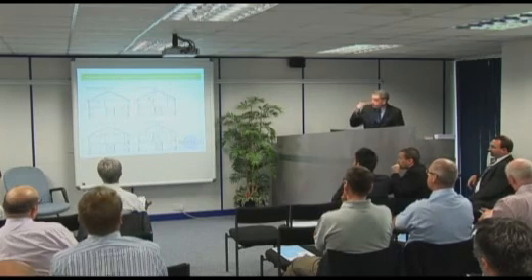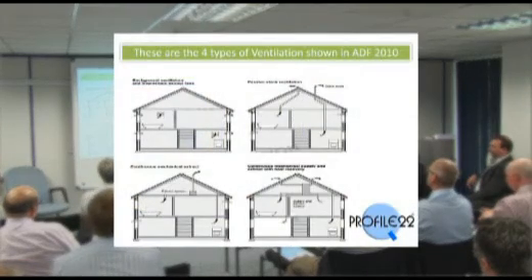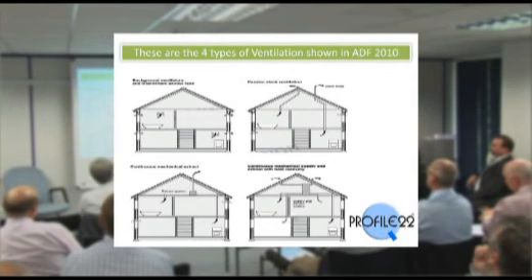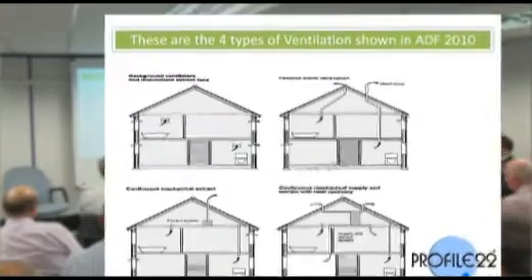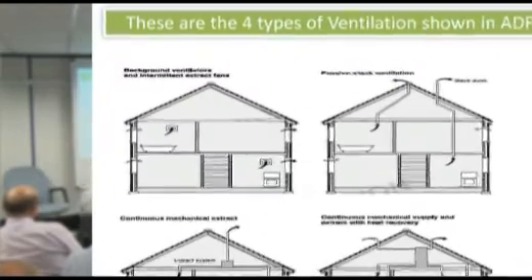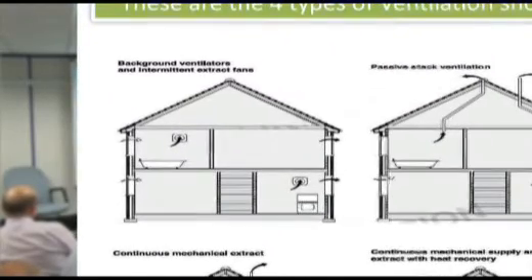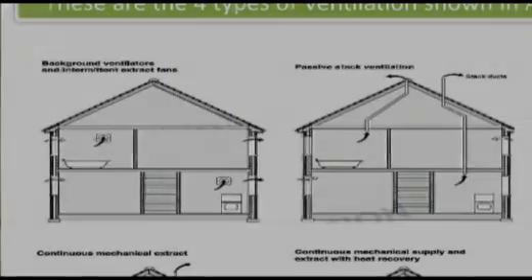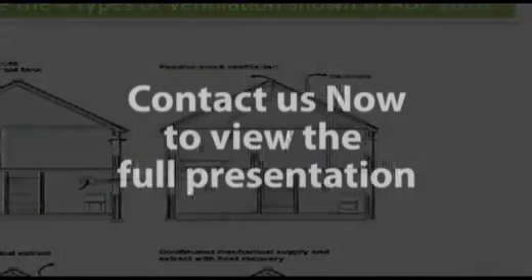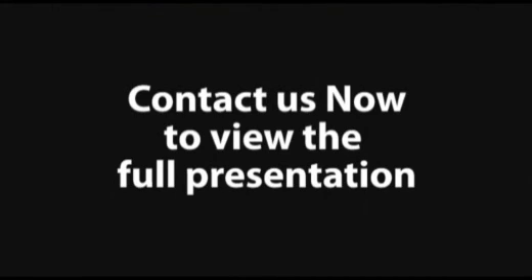Part F still has the same four major systems in place, although they do now allow an additional system, but that has to be proven through building control and planning. We have system one, which is probably used the most at the moment, which is background ventilation with intermittent extract fans. System two is a passive stack system, where we use flues to move the air through the property, again with background ventilation.